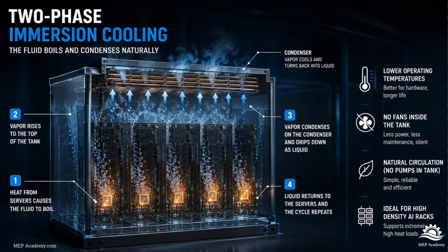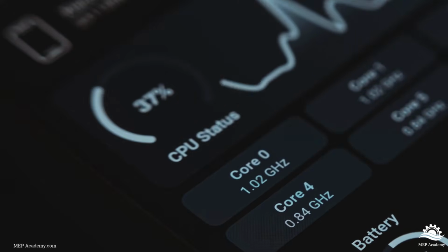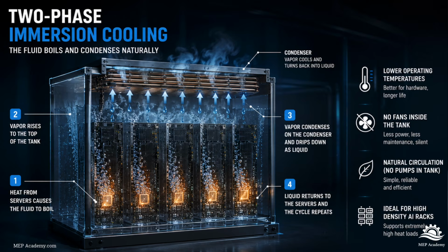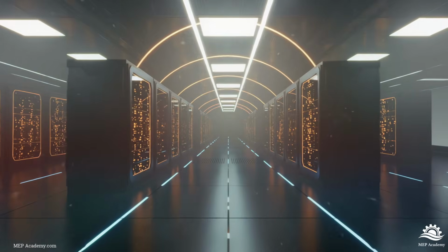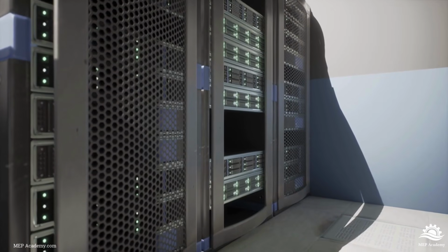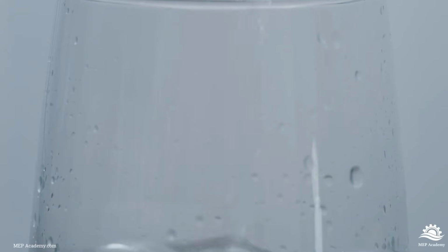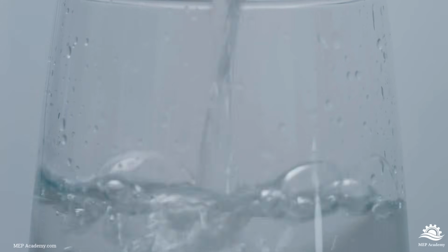Now let's look at two-phase immersion cooling. This is where things get interesting. The dielectric fluid is designed to boil at relatively low temperatures. As the processors heat up, the liquid begins to boil directly on the server components. That boiling creates vapor. The vapor rises upward. It contacts a condenser located at the top of the tank. The vapor cools, turns back into liquid, then drips back down onto the servers. No pumps are required inside the tank itself. If that sounds futuristic, that's because it is. You're essentially creating a miniature weather system inside every server tank.